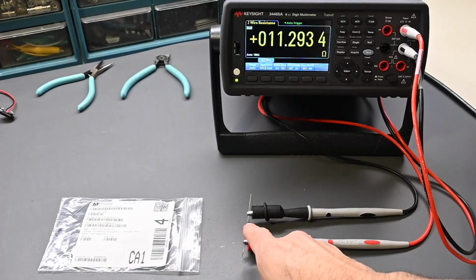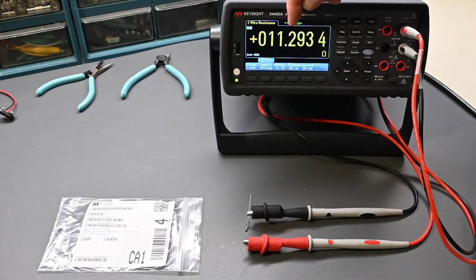So again, these 2 in parallel, you can see the reading that we're getting up here, very close to what we'd expect at 11.25 ohms, actually 11.2933. And I've nulled out the lead resistance again, so it says null right there on the display. Now again, the original resistor was rated at 11.2 ohms, 1% tolerance. So that means the original resistor could have drifted up as high as 11.312 ohms, or perhaps down as low as 11.088 ohms. So this value that we're seeing right here is well within the tolerance of what that original resistor would have been in. So I think paralleling these 2 together will work perfectly fine.